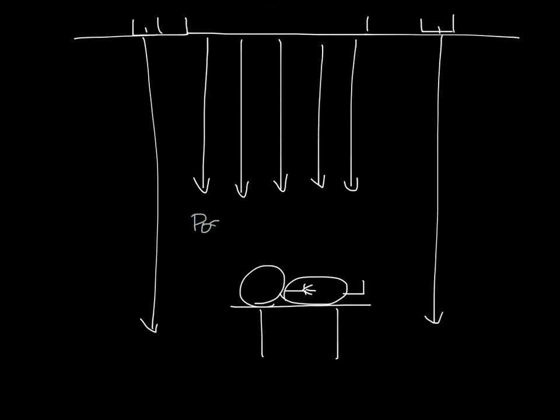You want the area inside the air curtain to have a higher pressure or be positively pressurized. This way, your particles will want to move from the higher pressure or the positive pressure to the lower pressure areas on the outside of the air curtain.